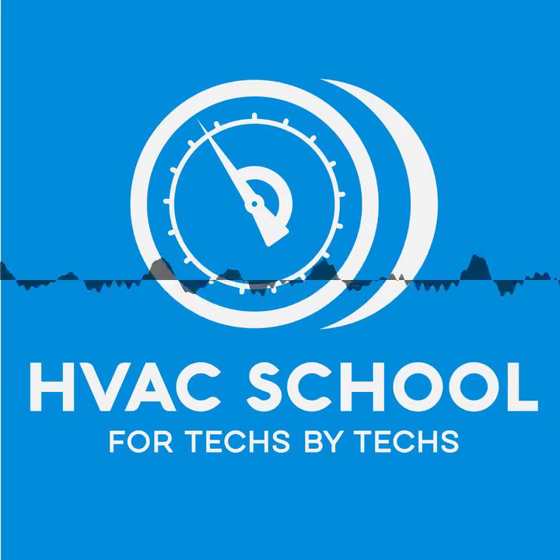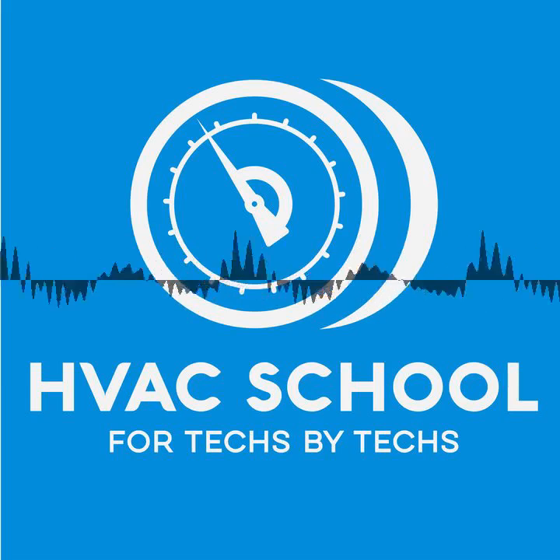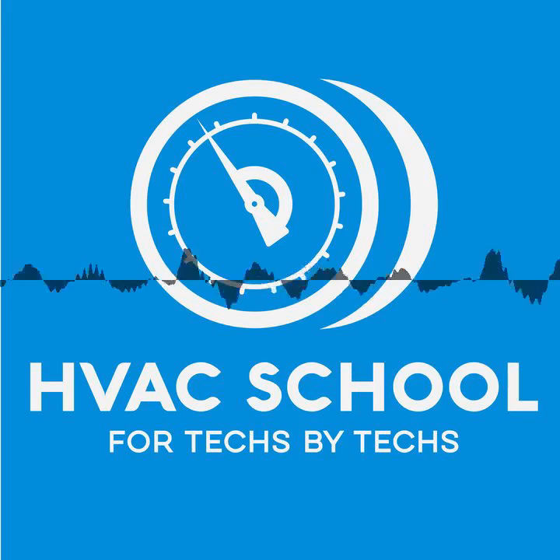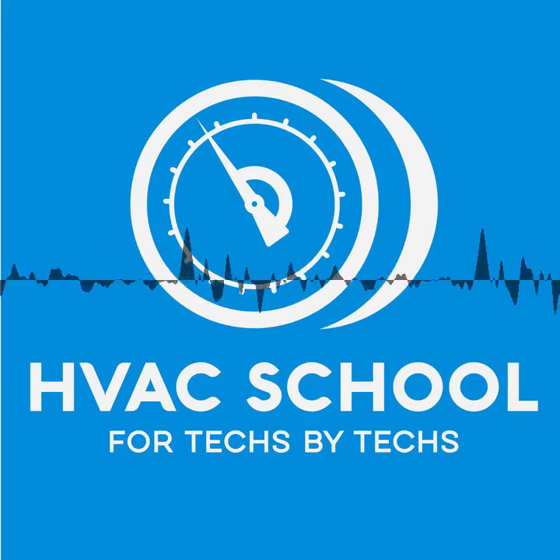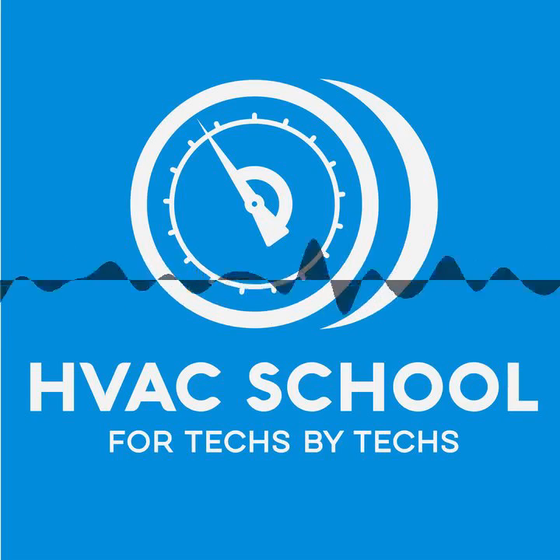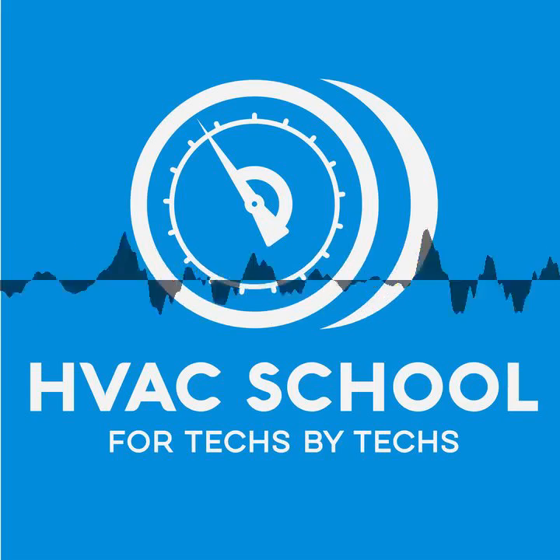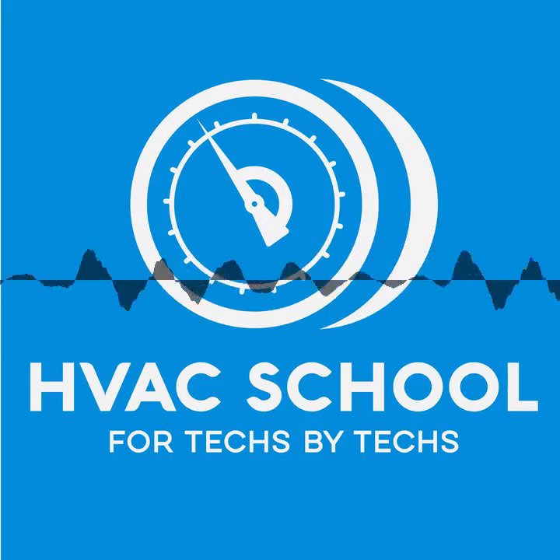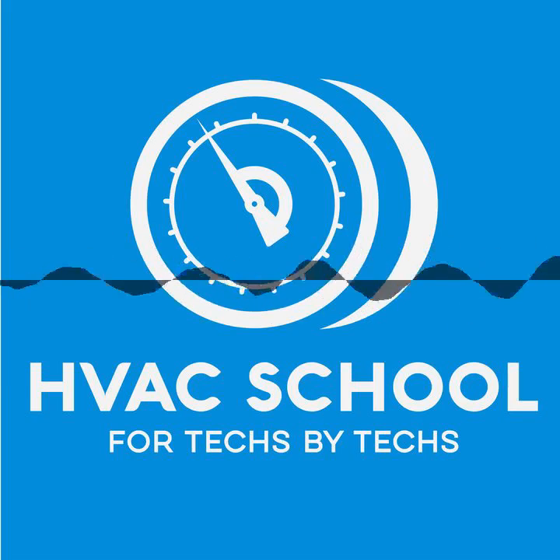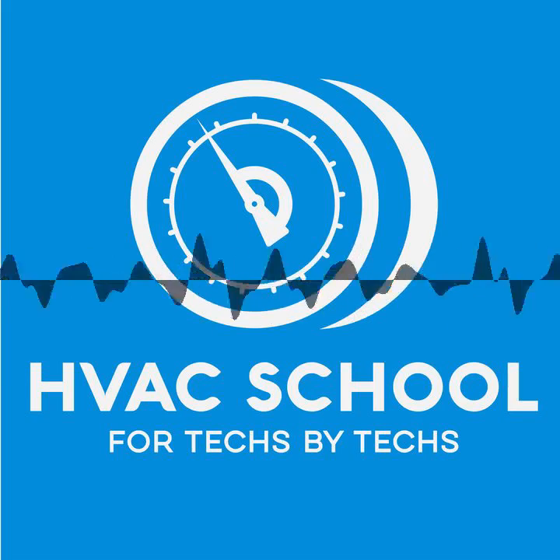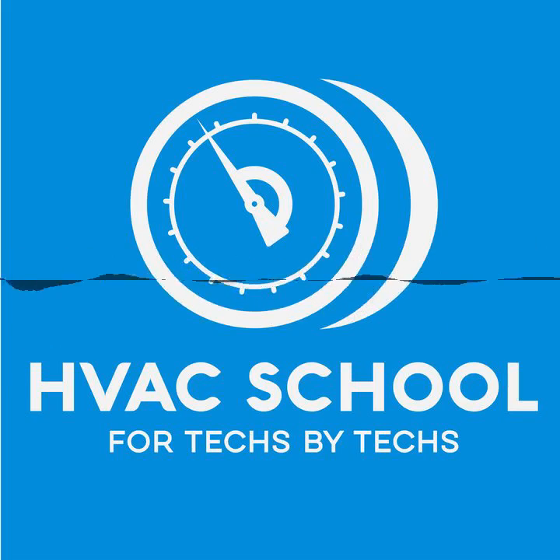Well, yeah. See, if it's plugged, then generally you can't force anything out of it. So when you try and push the diaphragm down, especially if it's got liquid in it, you can't compress a liquid. So you can't close that valve down, right? So it's literally going to stay in the one position it's in. That's a good point. I'm trying to visualize it in my head: if it's trapped with a high pressure underneath it, you can't relieve it. If it's trapped with a low pressure underneath it, you can't relieve it. So I guess it all depends on the throw of the die, right?